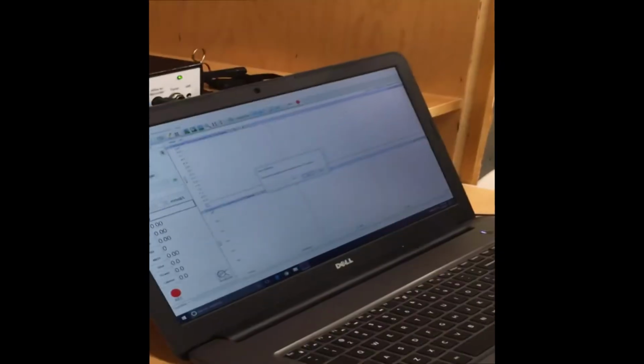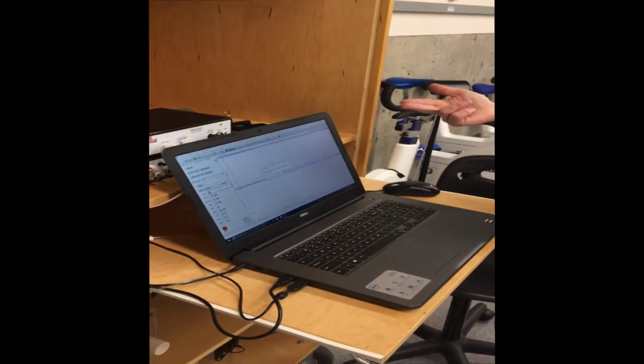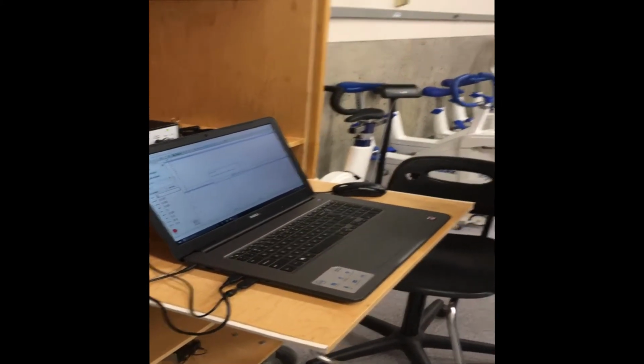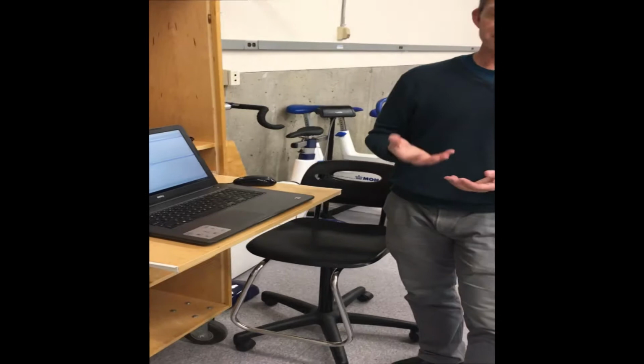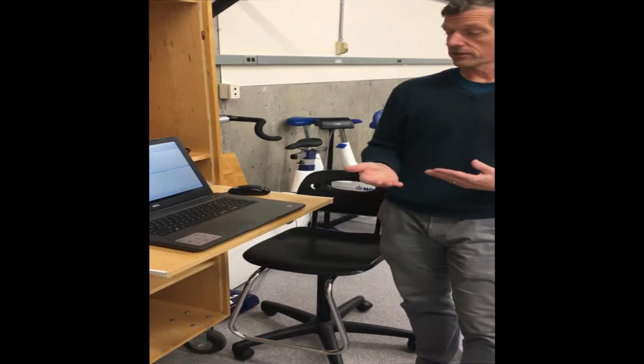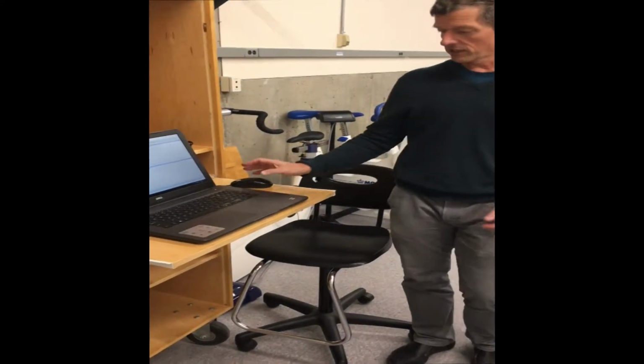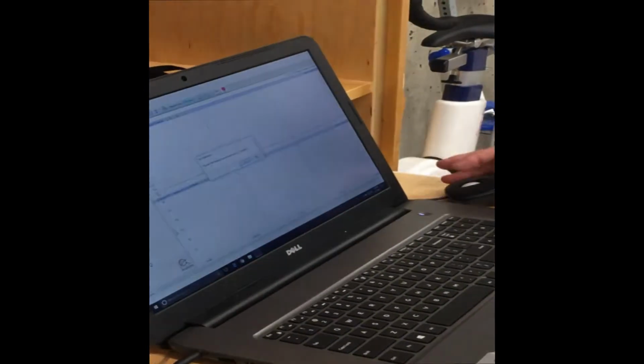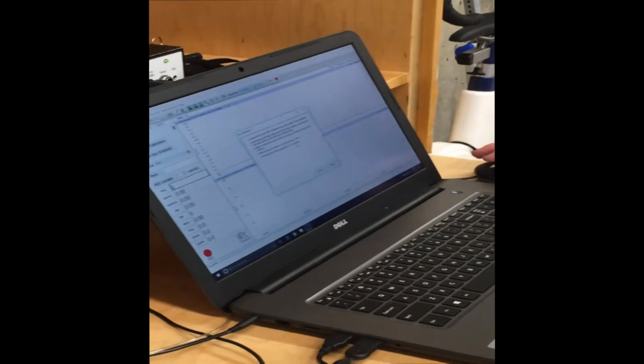And then it says, has the gas analyzer warmed up for 15 minutes? So for any gas analyzer, you typically want to have it warming up for at least 15 to 20 minutes, and there's a lot of gas analyzers that just stay on continuously. So we say yes, it has warmed up for 15 minutes. It typically won't even allow you to open up the program if the gas analyzer hasn't warmed up.